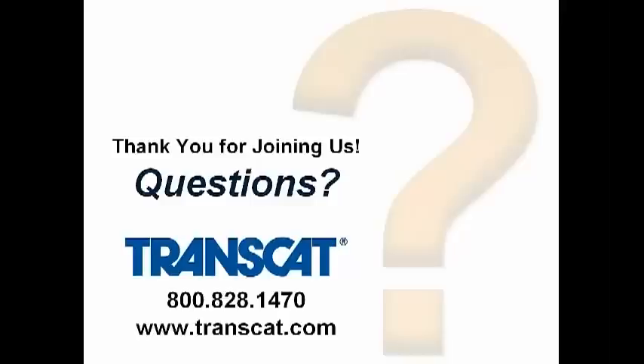When do we decide to adjust the equipment when it is near limit of tolerance? That's a very good question. We're in transition at this moment because that PCS tool that I mentioned is something relatively new that we've developed. And right now, our standard practice is to adjust at 75% of the limit. Now, typically, if you're at a 4-to-1 test uncertainty ratio, or TUR, 75% would be the adjustment limit so that you're not into the guard band region. If you're not familiar with these terms, I recommend that you read our K = 3.9 white paper on our website.